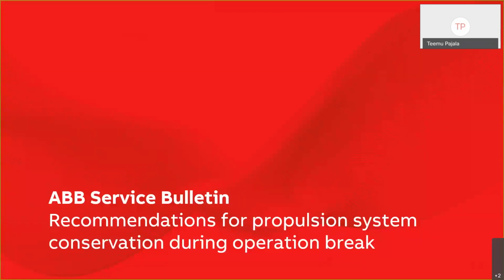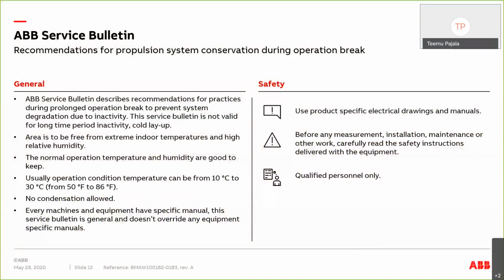Then in the next slides, we go more to ABB's instructions, what is given in the service bulletins. The first section covers hot and warm layup condition. In general, these are recommendations for practices during operational breaks. The first service bulletin, whose reference number you see at the bottom of the screen, is not valid for a long period of inactivity, which is called cold layup and has its own instruction.